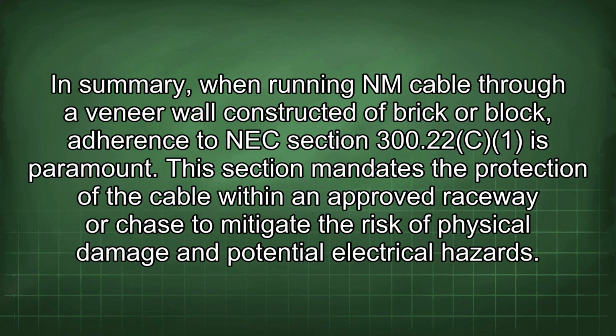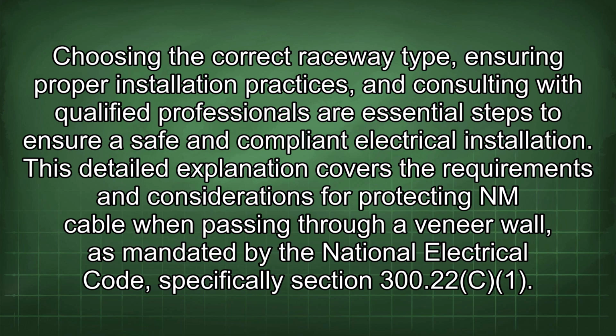In summary, when running NM cable through a veneer wall constructed of brick or block, adherence to NEC section 300.22(C)(1) is paramount. This section mandates the protection of the cable within an approved raceway or chase to mitigate the risk of physical damage and potential electrical hazards. Choosing the correct raceway type, ensuring proper installation practices, and consulting with qualified professionals are essential steps to ensure a safe and compliant electrical installation.